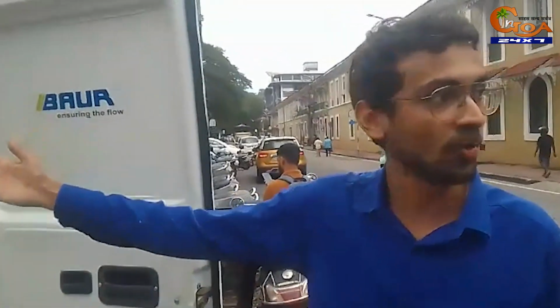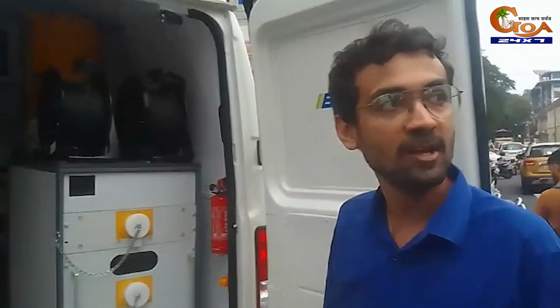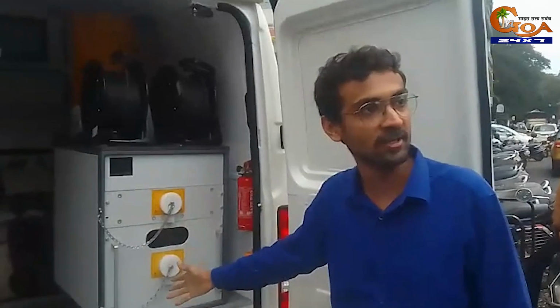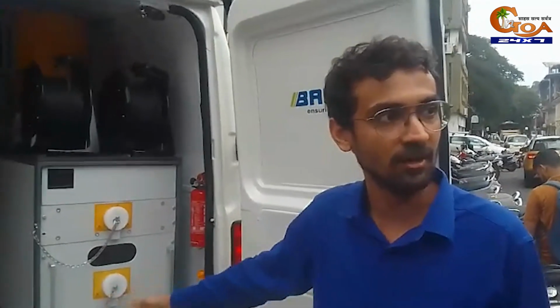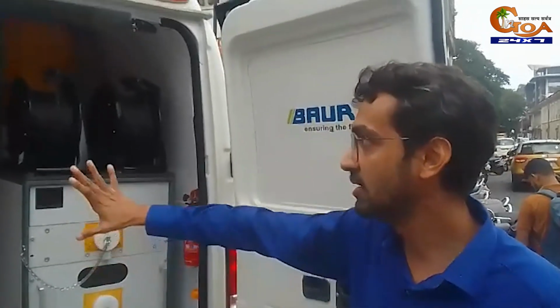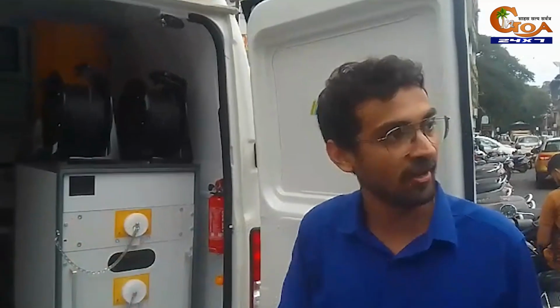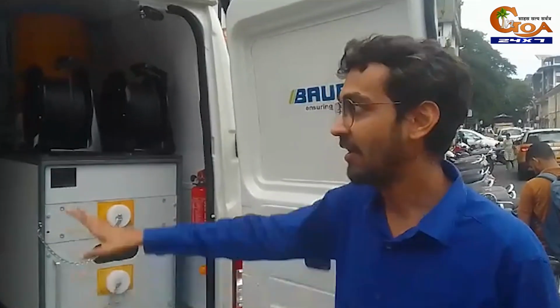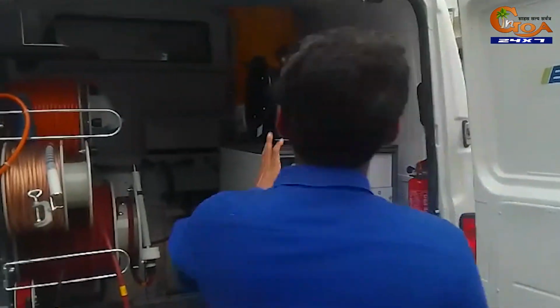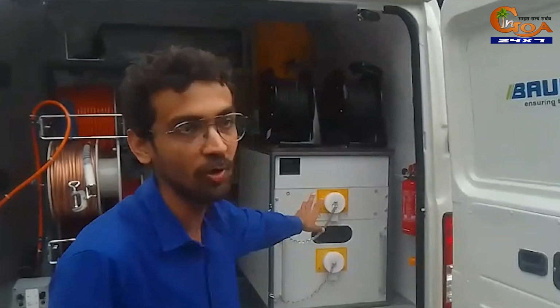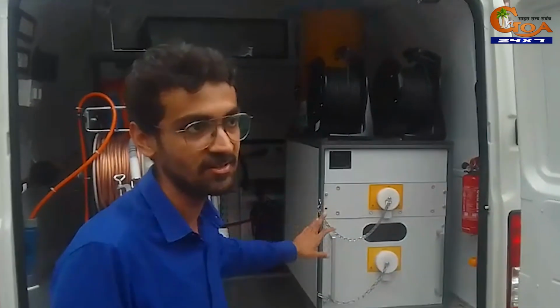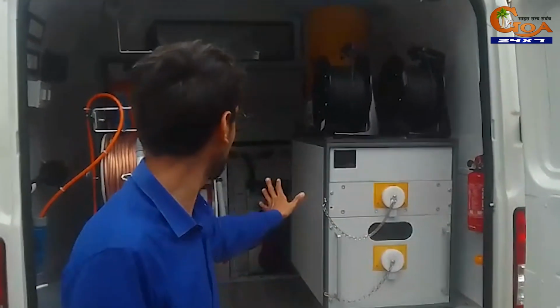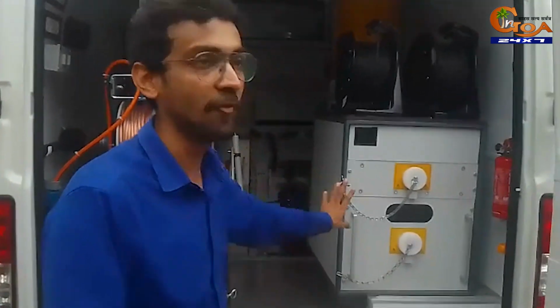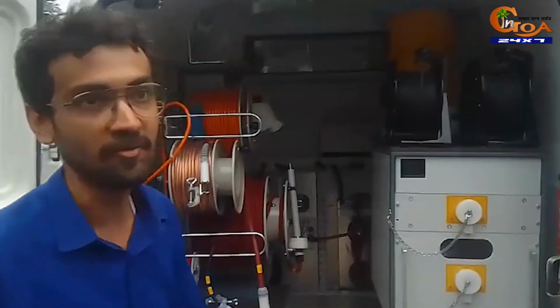This is a fully automatic cable fault locating van. We have supplied it to Goa Electricity a few days ago, last week. This van is for locating underground cable faults, and it is equipped with tan delta and partial discharge testing. We can do VLF testing as well as DC pressure testing, around 80 kV DC voltage and 57 kV VLF.